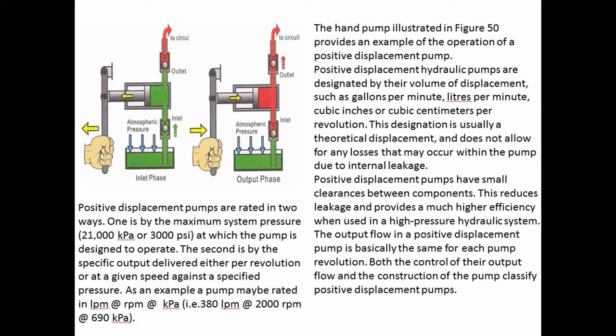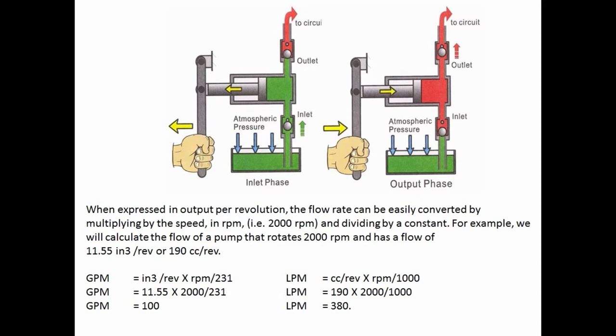Positive displacement pumps are rated in two ways: first, by the maximum system pressure (21,000 kilopascals or 3,000 PSI) at which the pump is designed to operate; second, by the specific output delivered per revolution or at a given speed against a specified pressure. For example, a pump may be rated at 380 LPM at 2,000 RPM at 690 kPa. The flow rate can be converted by multiplying by speed in RPM. For a pump rotating at 2,000 RPM with displacement of 11.55 in³/rev (190 cc/rev): GPM = (in³/rev × RPM) ÷ 231; LPM = (cc/rev × RPM) ÷ 1,000. Result: GPM = 100; LPM = 380.